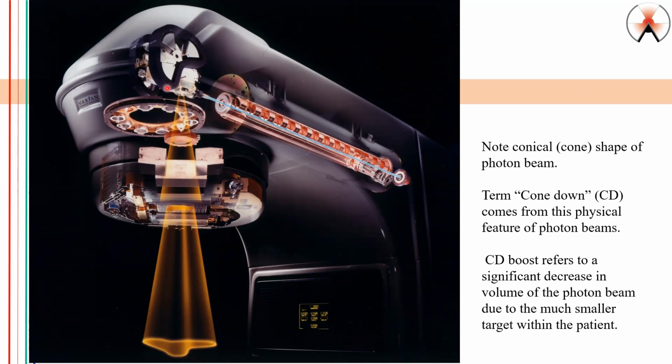So it turns here, that's a 90-degree turn, another 90-degree turn, and another 90-degree turn in a downward direction, where we make that electron beam collide with a metallic solid object. We call that a target. In a linear accelerator, that solid object is a tungsten target.